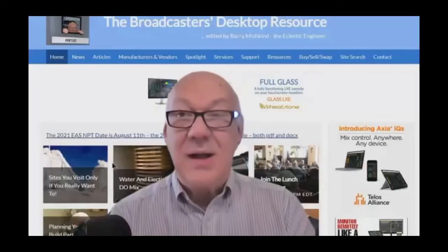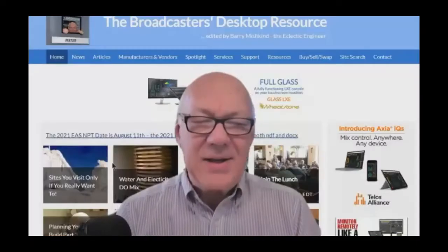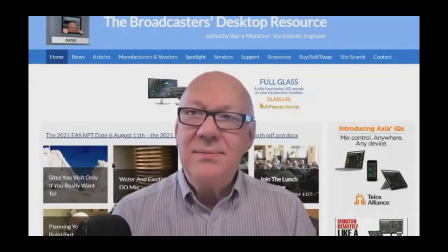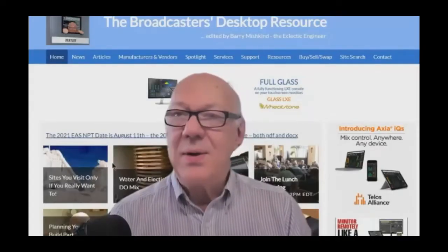Well, another thing with generators, particularly in some states like maybe California, is you need to start logging how many hours it runs per month and per annum because of pollution concerns. Oh boy. I don't do that because I'm in Texas, but even Dallas has gotten real big on that. You need to log your hours in the big cities because everybody is on some kind of air threshold warning. Some agency is threatening their funding if they don't get it cleaned up. Yep. So would this be a separate log in this case, David? I would do it that way just because somebody's going to look at it, and you don't want the city messing around with your other activities. Yeah, or the TCEQ or whoever.